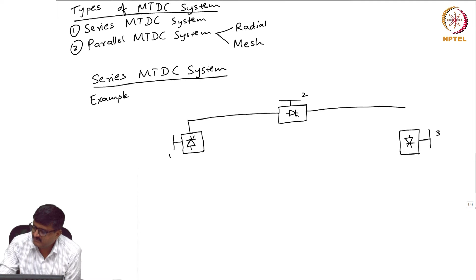Now, what I am trying to say is this is an example of a series MTDC system. That means the DC current is same in all the three converters. If I want one of them to operate as a rectifier, at least one should operate as rectifier, at least one should operate as inverter. Suppose we decide some converter to operate as rectifier. How do we get that rectifier operation? That is obvious, alpha. If we know that alpha close to 0 is rectifier operation, alpha close to 180 degrees is inverter operation, then depending on the choice of alpha, we can ensure that we get the required operation.